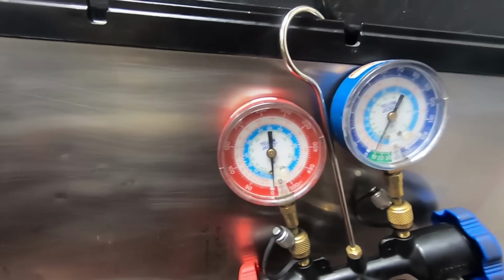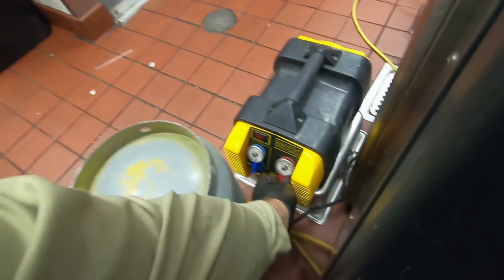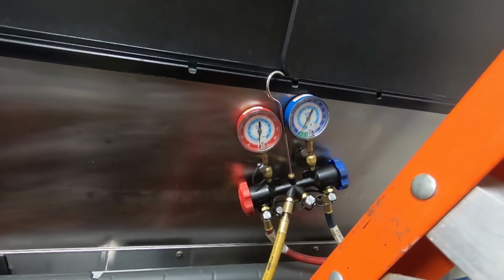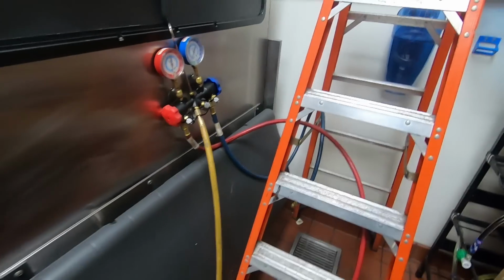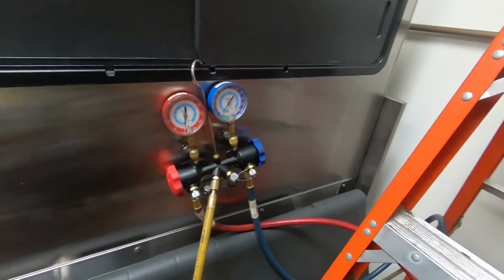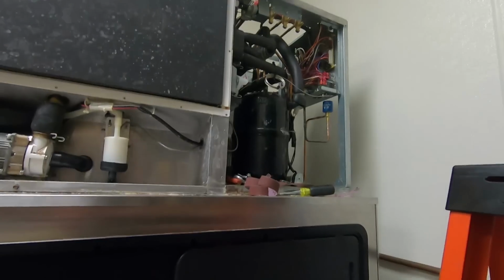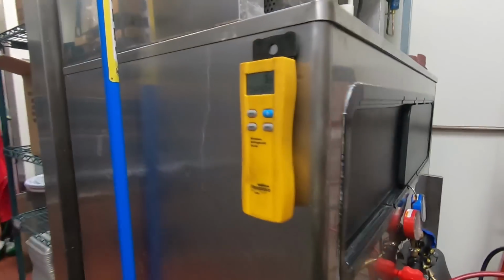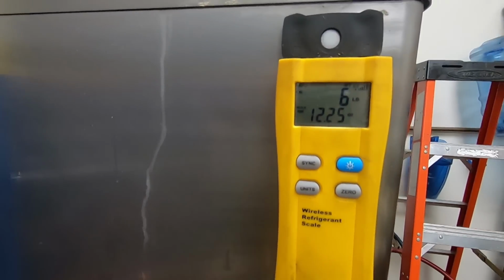Even though this unit has a leak, I'm not going to reuse the refrigerant. So we're just about done now. What I'll do is shut off the machine and the outlet and see if our pressures rise. We'll give it a second to see if they rise up. If they don't, we'll be good. The pressures didn't rise above positive, so I went ahead and took the hoses off. Definitely we're short. All right, cool.